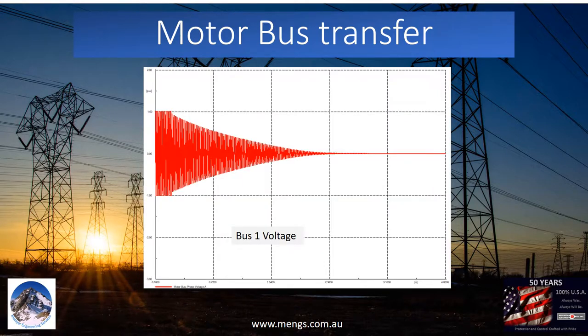Opening the main 1 circuit breaker doesn't mean bus 1 voltage drops to zero immediately. The voltage on bus 1 slowly decays; the rate of change depends on the electromagnetic time constant of the motors connected to the bus. In most cases, it will take 2 to 3 seconds for the voltage to drop to under 10% of nominal voltage. The presence of this residual voltage is due to the voltage generated by the motors.